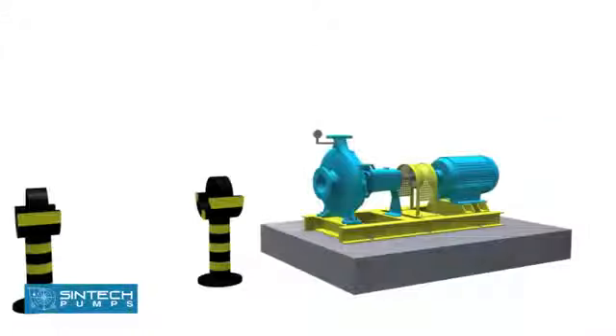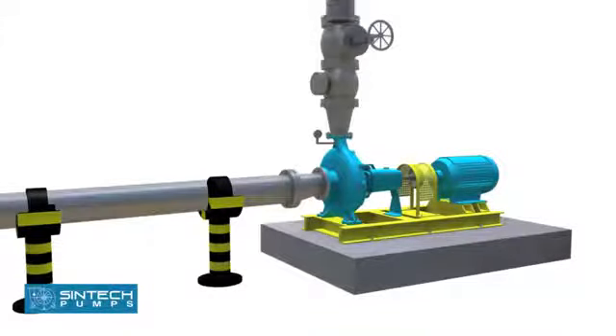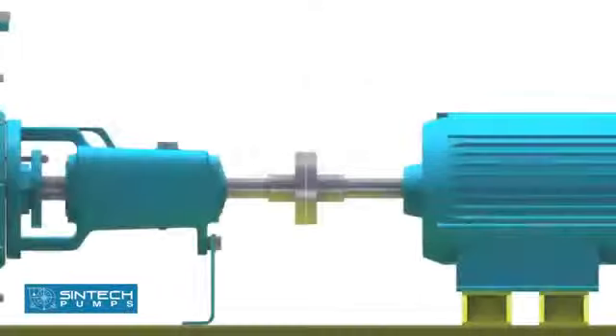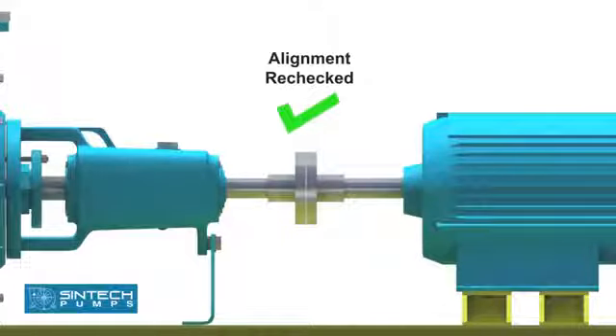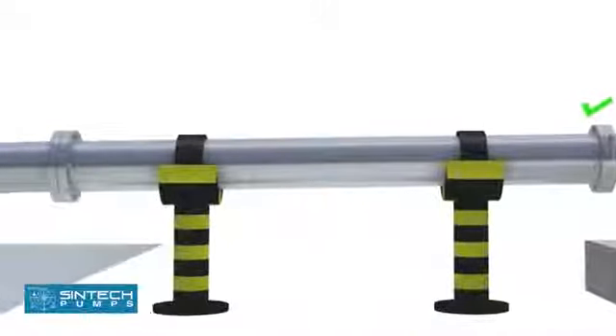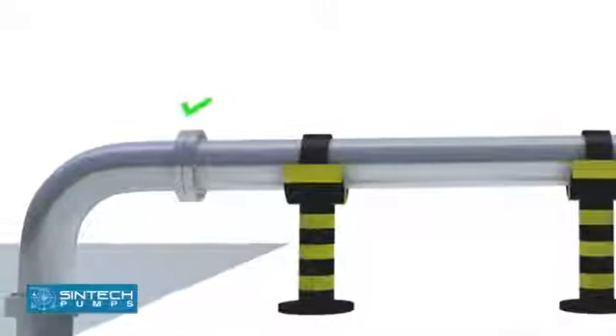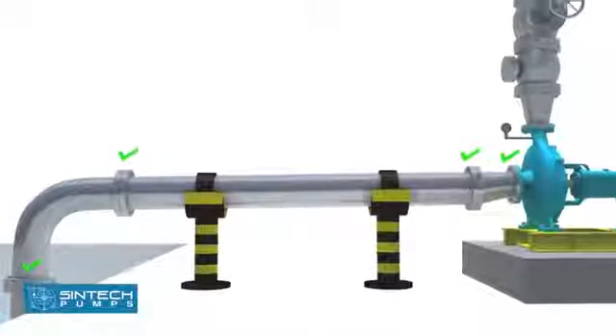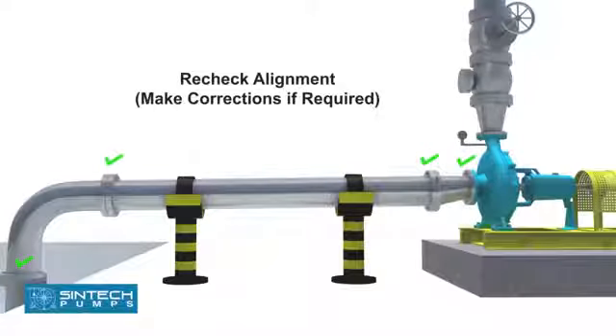After the alignment is completed, the piping associated with the pump should be bolted. Once this is completed, the alignment should be rechecked and similar readings should be obtained. If this is not the case, then the piping should be investigated and suitable corrections made. If left unattended, it can cause stress on the pump casing.